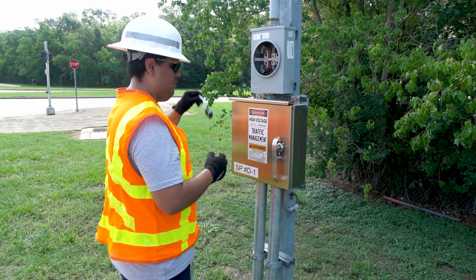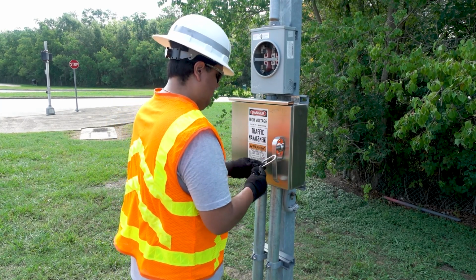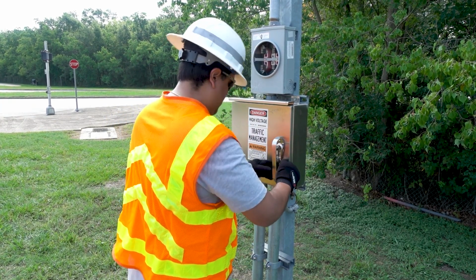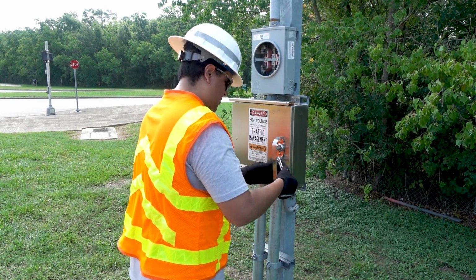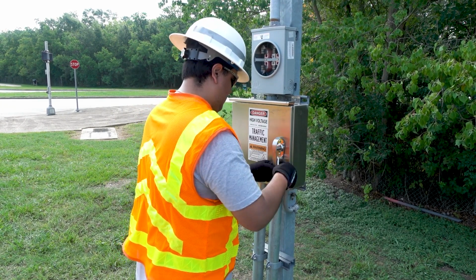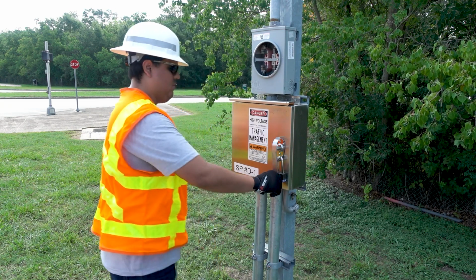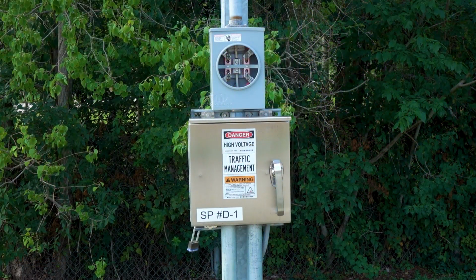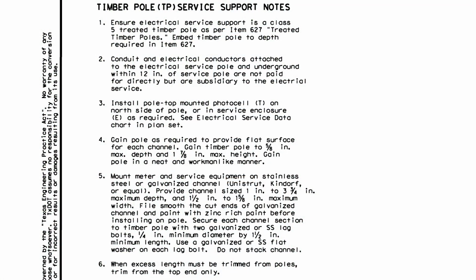The enclosure's purpose is to provide protection from the weather for the electrical parts and to keep unauthorized persons away from potentially dangerous electrical energy. The next item of inspection will be the mounting and securing of the enclosure to the support structure. When a timber pole is called for by the descriptive code, the pole is to be notched or gained in accordance with the details listed in the upper left corner of ED10.